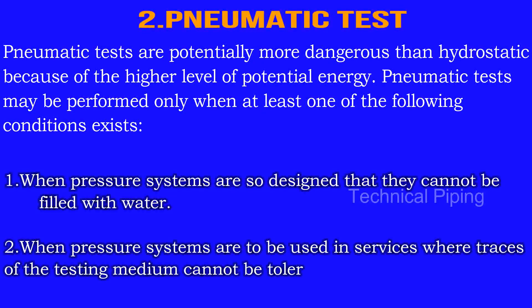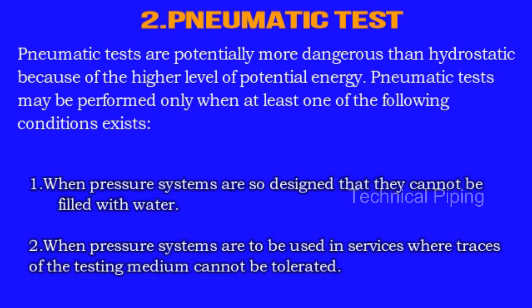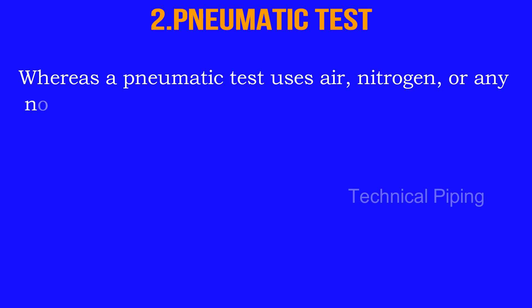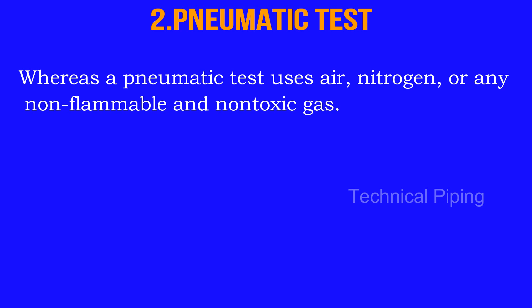Number 1: when pressure systems are so designed that they cannot be filled with water. Number 2: when pressure systems are to be used in services where traces of the testing medium cannot be tolerated. The testing medium for pneumatic test uses air, nitrogen, or any non-flammable and non-toxic gas.